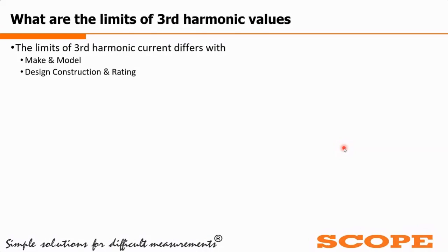Now, as per the WHO standard or the national standard, there are some limits. Generally, a healthy human could be 5.5 feet tall, which is the standard height in the Indian scenario. 5.5 is the average height, and average weight is 65 kg plus or minus something, or 70 kg, plus or minus. So similarly, the limits of third harmonic current will differ with make and model, design, construction, and rating of the LA.